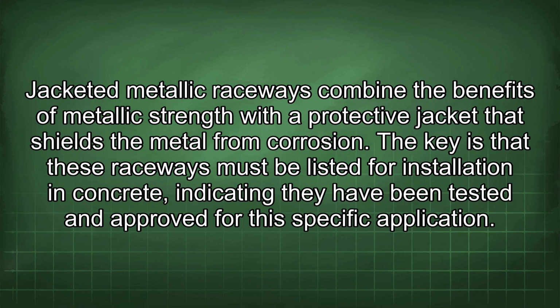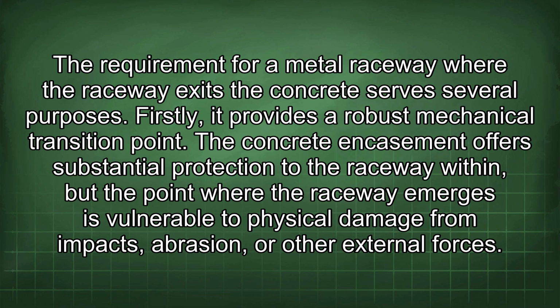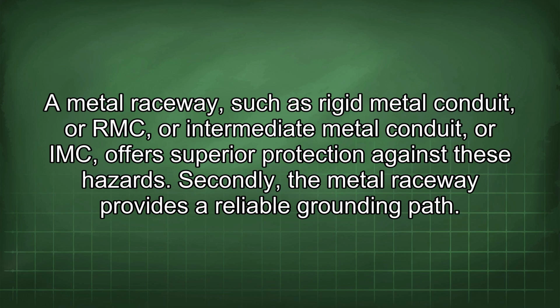for the specific application. The requirement for a metal raceway where the raceway exits the concrete serves several purposes. Firstly, it provides a robust mechanical transition point. The concrete encasement offers substantial protection to the raceway within, but the point where the raceway emerges is vulnerable to physical damage from impacts, abrasion, or other external forces. A metal raceway, such as rigid metal conduit, or RMC, or intermediate metal conduit, or IMC, offers superior protection against these hazards. Secondly, the metal raceway provides a reliable grounding path.